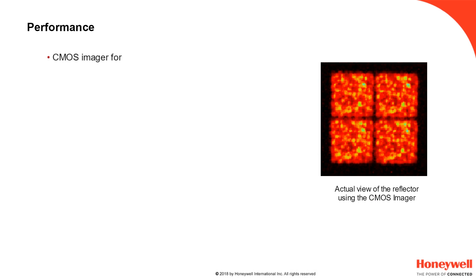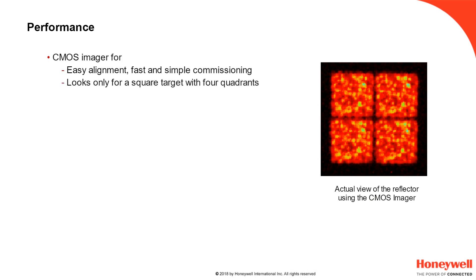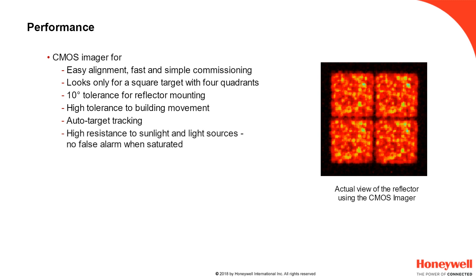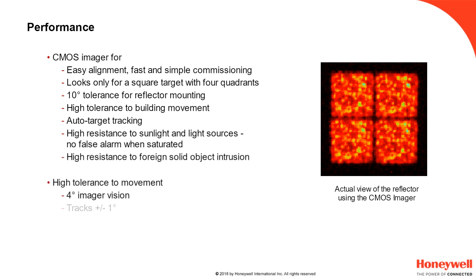One of the keys to the OSID R's performance is its use of a CMOS imager rather than the traditional photo receiver. A photo receiver has an effective resolution of 1 by 1 pixel. The CMOS imager has many thousands of pixels and produces an image of the field of view seen by the device, which the software can interrogate and interpret. This interpretation allows the simple alignment process and supports tolerance to alignment issues, building movement, and false alarms caused by sunlight or intrusion.